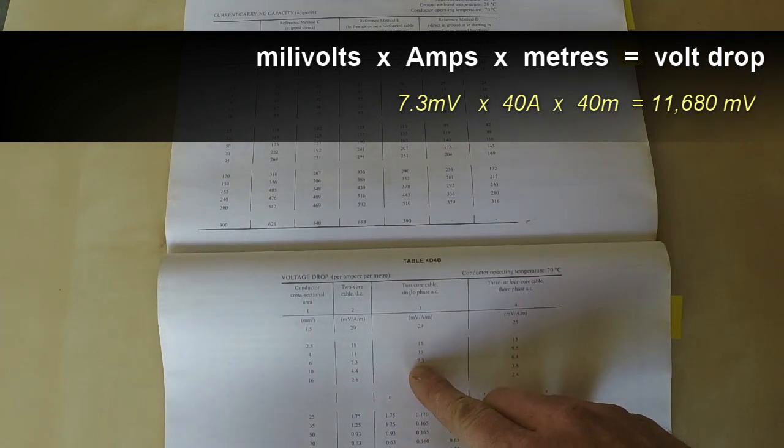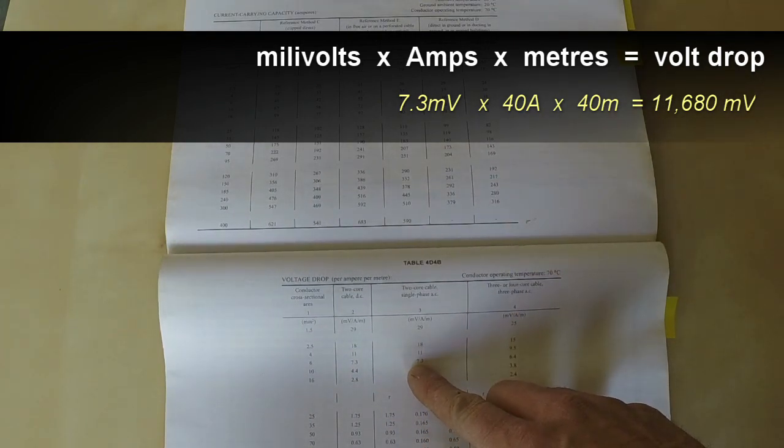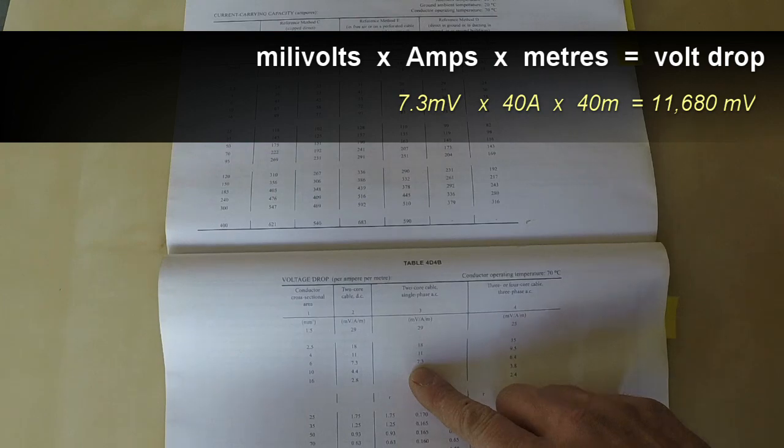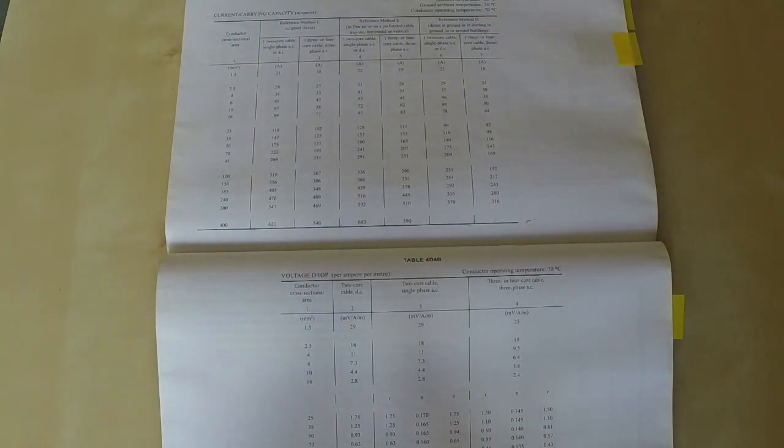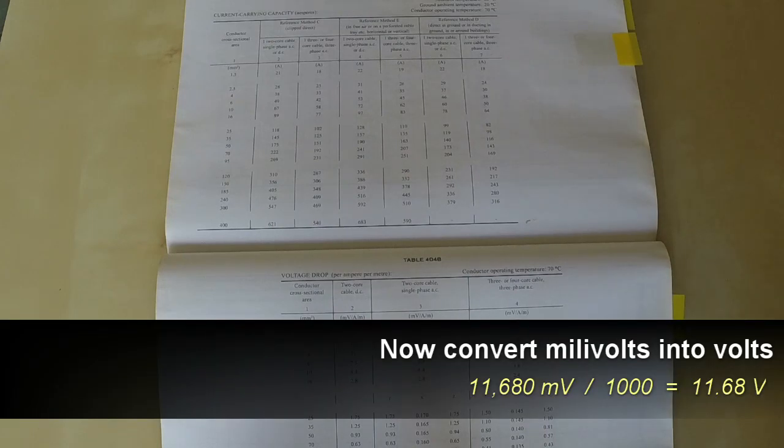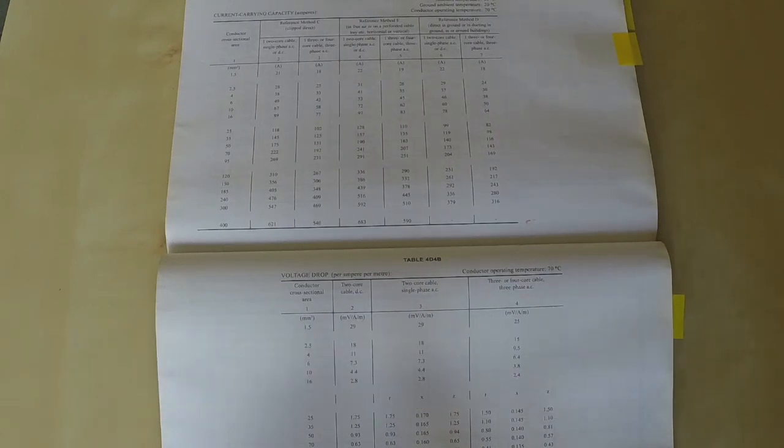Times your 40 meters times 40 amps. Now that gives you 11,680 millivolts. Because we work in volts, we need to convert that into volts, so divide it by a thousand because the 7.3 is in millivolts. That gives you 11.68 volts.